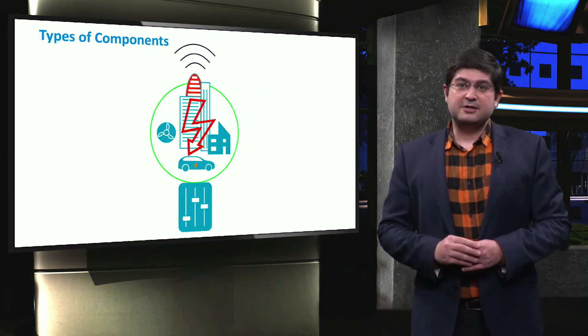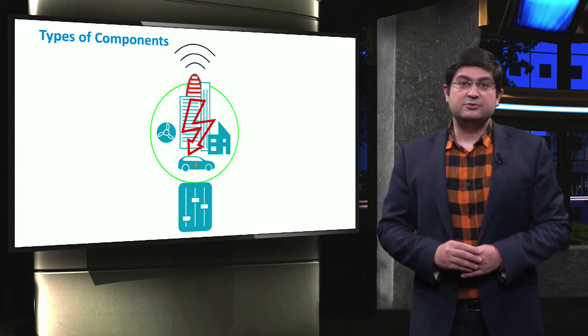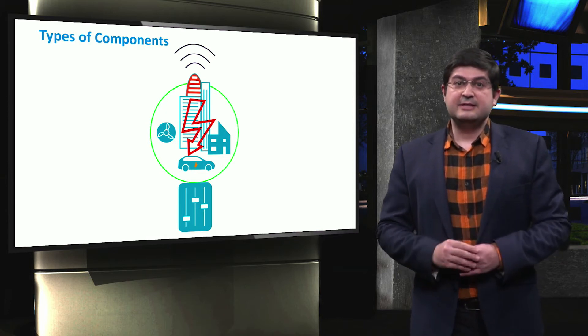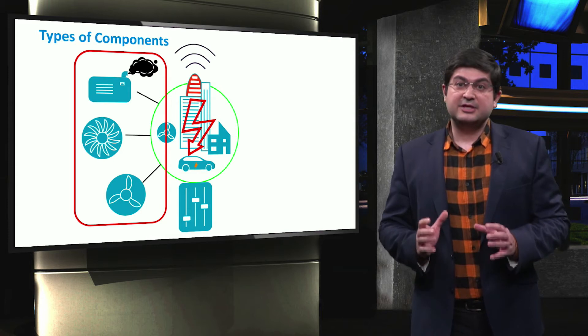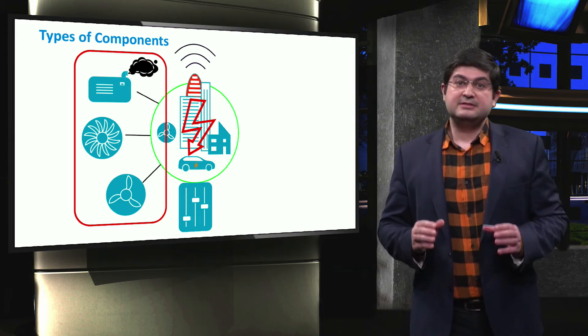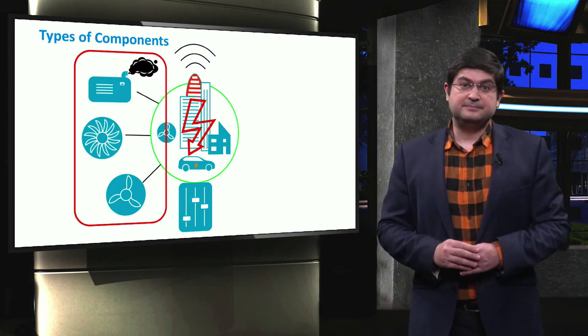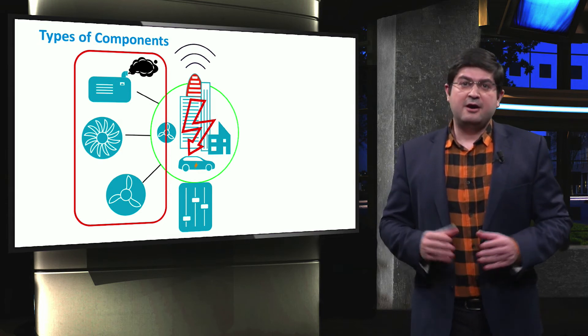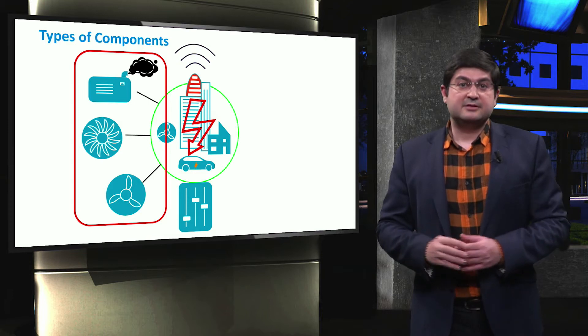We discussed that microgrids shall be able to isolate the internal faults using proper protection methods. If the fault is not quickly cleared, then some electrical equipment might be damaged. Also, this delay associated with the protection system may result in the instability of the distributed generators based on direct electrical machines. Diesel engines, microturbines, and gas turbines are examples of these distributed generators.